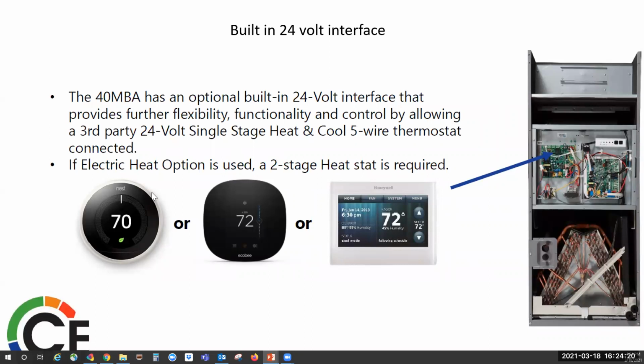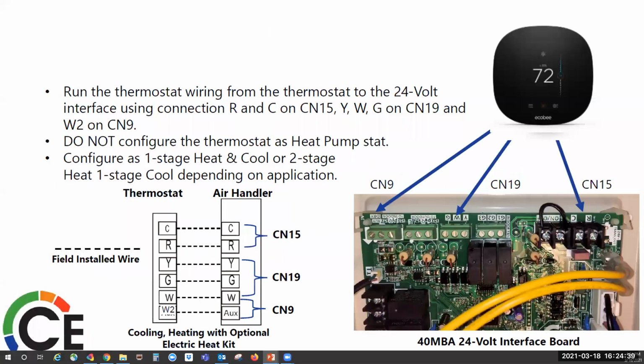So if you don't want your electric heat coming on at the same time your heat pump does, you'll have to put in a relay, and I will talk a little bit more about that down the line here. Obviously, when you're running a thermostat, you're going to follow the installation manual from the 24-volt interface kit, and it's pretty straightforward.